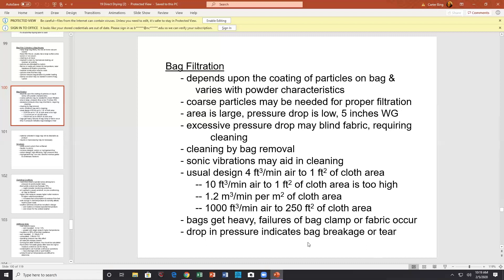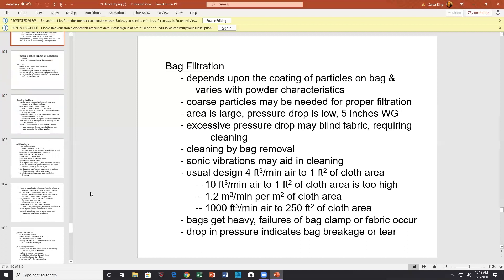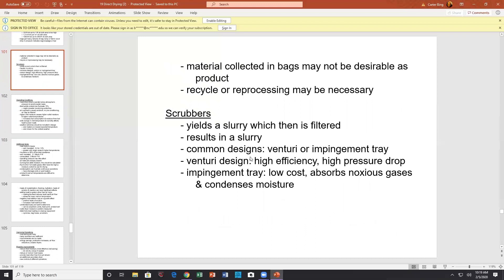The usual designs given four cubic feet per minute. One foot square cloth area. Do you have this information for your bags? Bags are heavy, get heavy failures. Bag clamps is often the case. Fabric, also a failure of the fabric. I mean, your bag house may be 50 years old and the fabric has rotted. But, hopefully you're not in that situation. 50 year old bag houses. Drop in pressure indicates breakage, so you monitor the pressure. You also have such devices as the triboflow particle detector. It's kind of cool. Material collecting bags may not be desirable as a product. Recycle reprocessing may be necessary though. Wet scrubbers. It's a slurry that then has to be filtered. Common designs venturi impingement plate. High efficiency, high pressure drop. Low cost, absorbs obnoxious and condenses. Moisture.